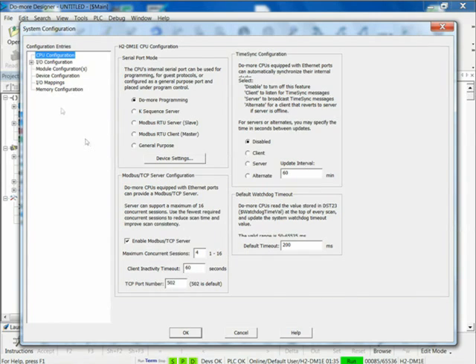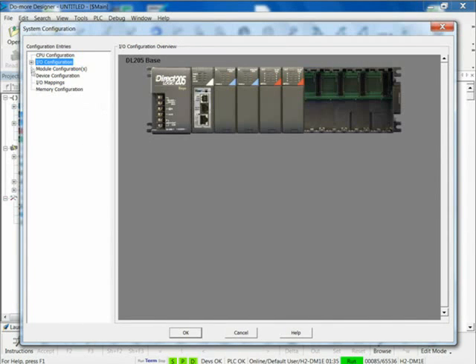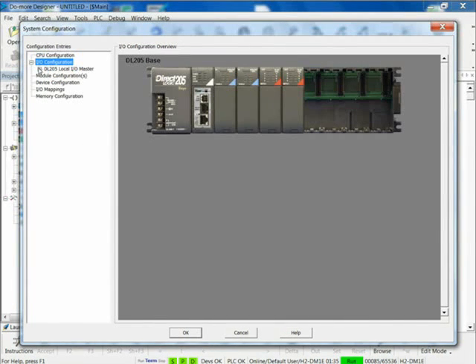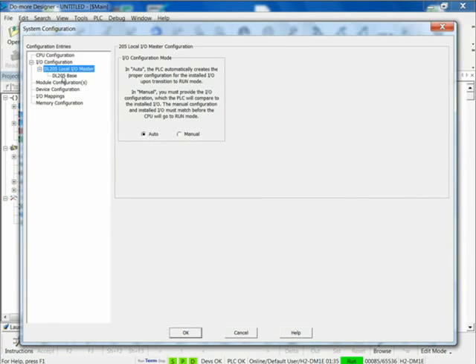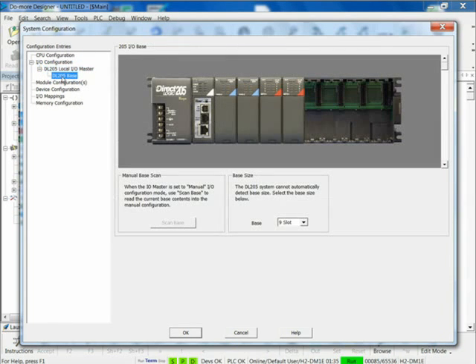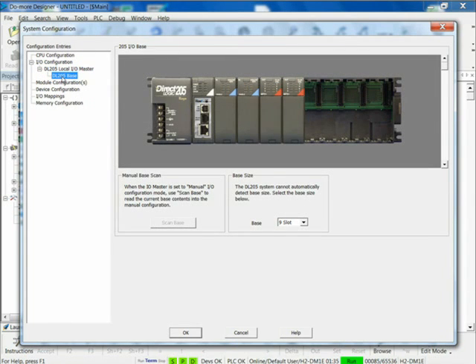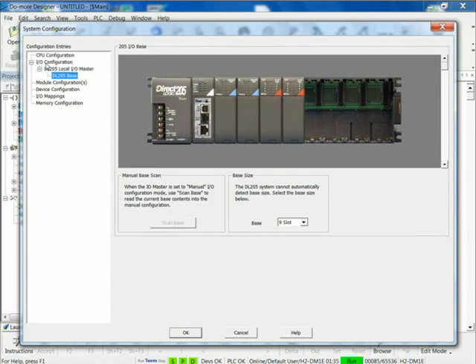The next one down is I/O configuration. And that gives me a picture of the I/O rack. It actually shows me what's sitting out there. It's an actual tree where you can go in here and set up some manual addressing if you want to, but most of the time you just want to automatically scan your base. So you just plug it in and it works.